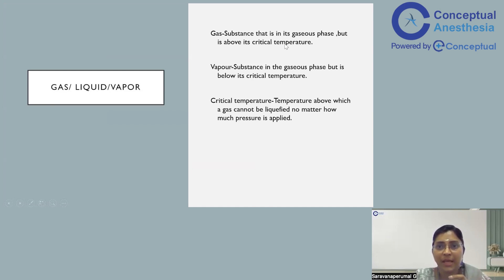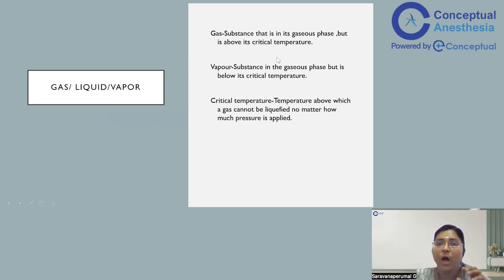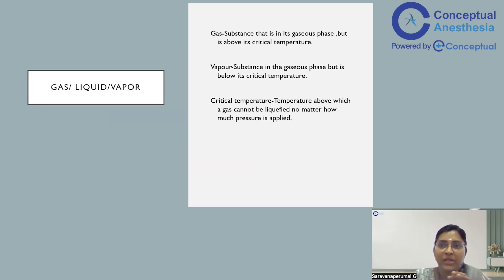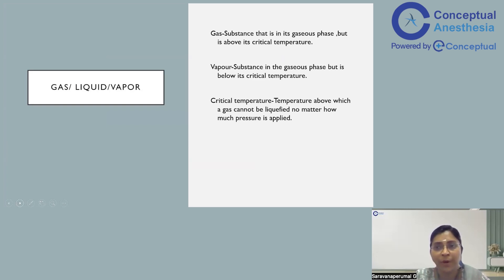What is a gas? It is a substance that is in a gaseous state above its critical temperature. Vapour is a substance which is in gaseous phase below its critical temperature. Critical temperature is the temperature above which the gas cannot be liquefied no matter how much pressure you apply. The critical temperature of nitrous oxide is 36.5 degrees Celsius and for oxygen it is around minus 118 degrees Celsius. For all practical purposes, oxygen supplied in our setting exists as a gaseous form, except for liquefied oxygen available in liquid oxygen tanks.